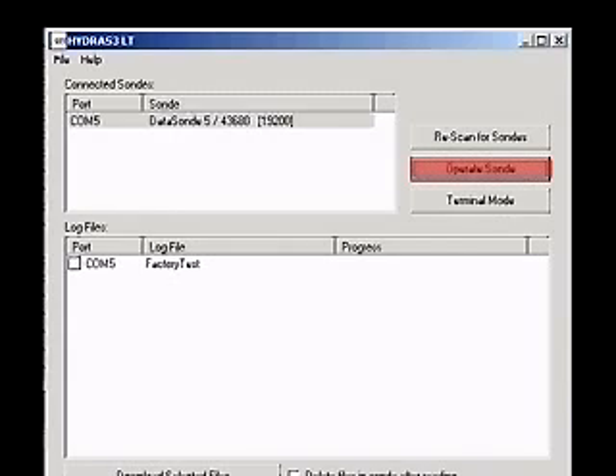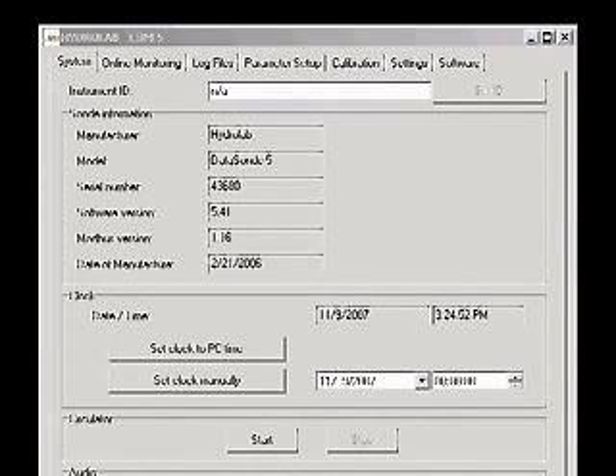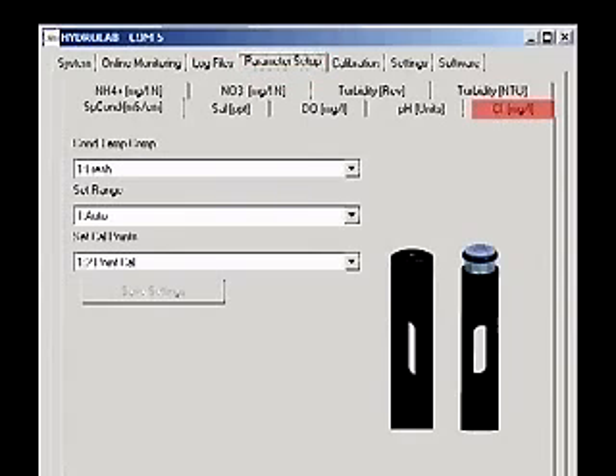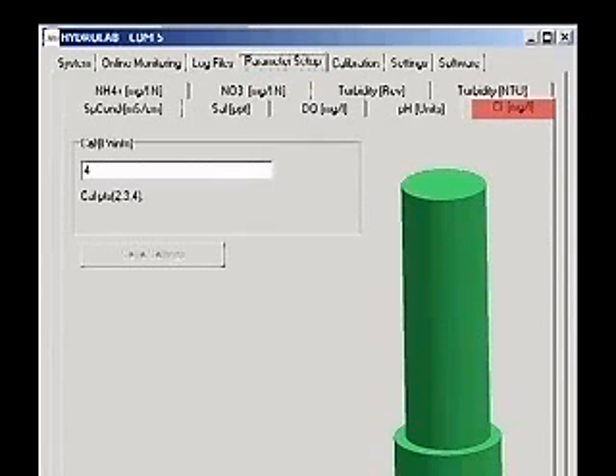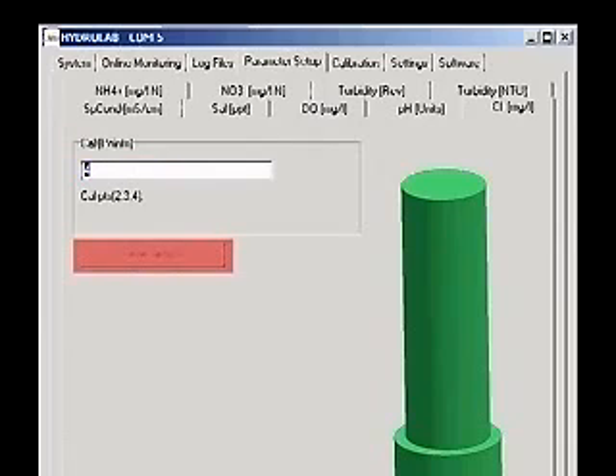Establish a connection to the sonde with HYDRAS3LT. Click the button labeled Operate Sonde. When the sonde finishes its initialization, check the Parameter Setup tab. Then click the Chloride Milligrams per Liter tab. Type the number of calibration points you are using in the box and click Save Settings. If you change the number of calibration points, you will need to close the Hydrolab window and reconnect to the sonde for the change to appear on the calibration screen.